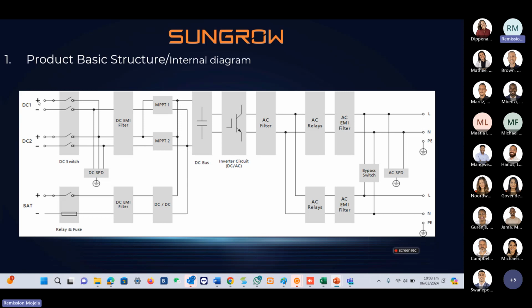We have the DC switch from the beginning, but before the DC switch, there's the arc detection board that is sitting in front of the system to protect the system from faults, as well as arcs that come from the strings. Basically, any loose connection or arcing will be stopped before it even gets to the DC switch. And that's one of the things that Leonard was mentioning about the arc detection fault on the system.